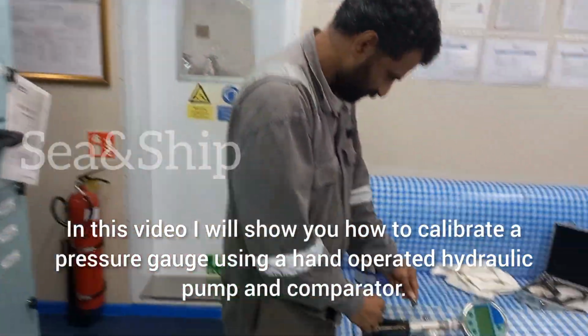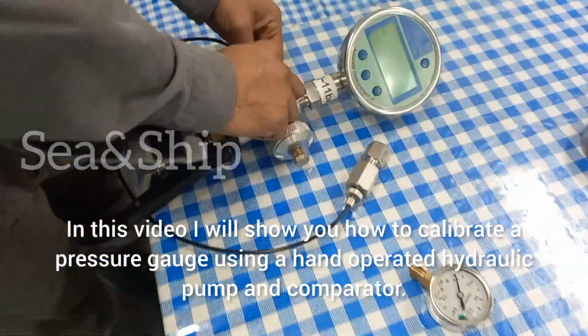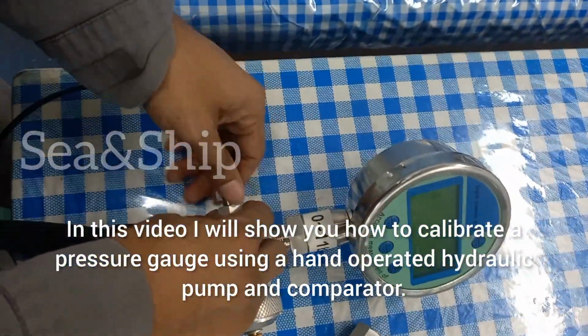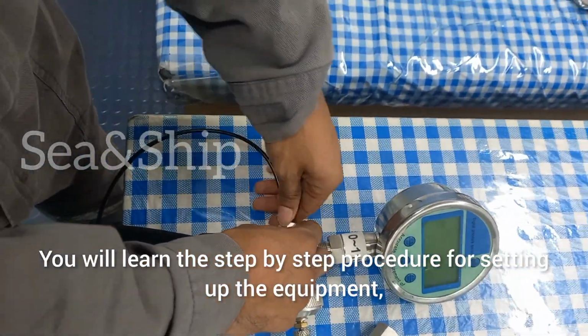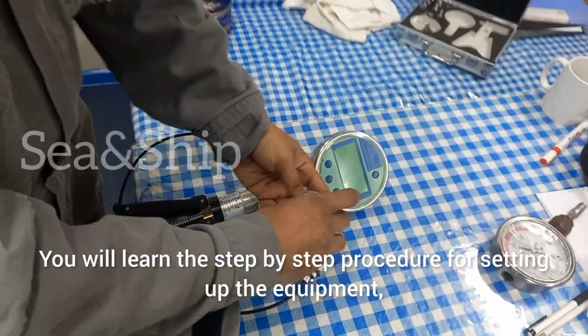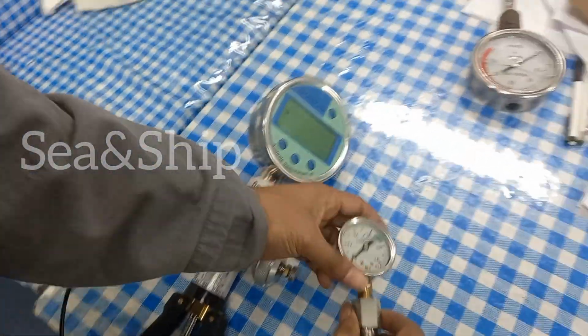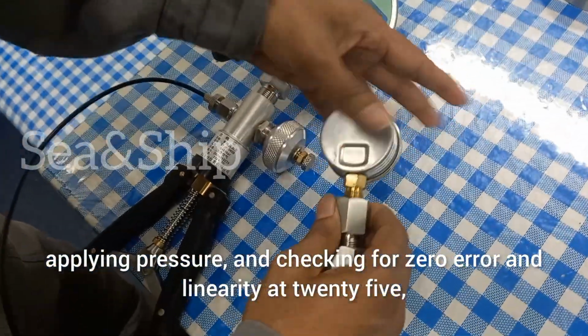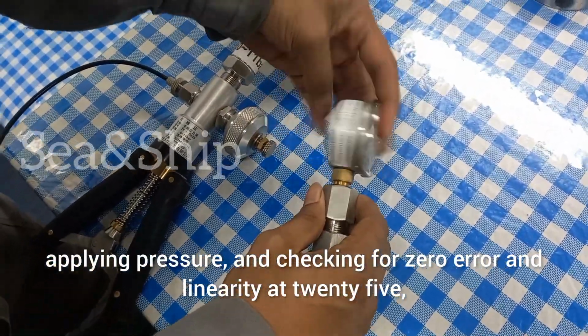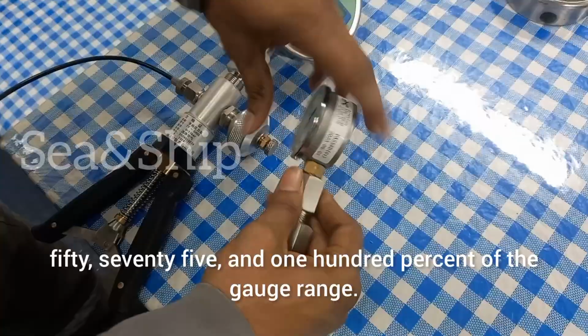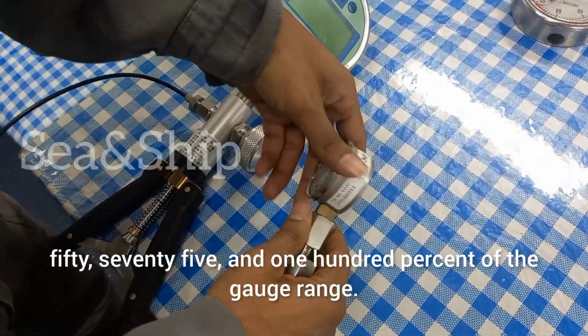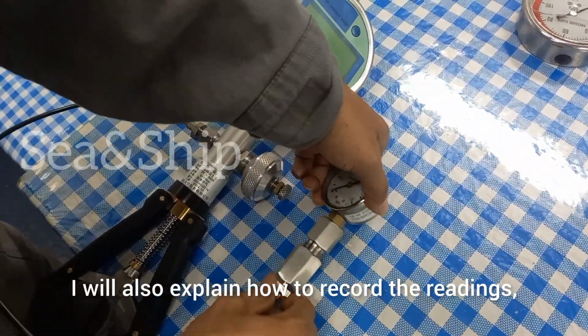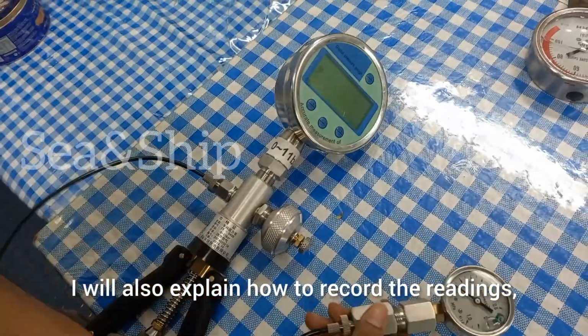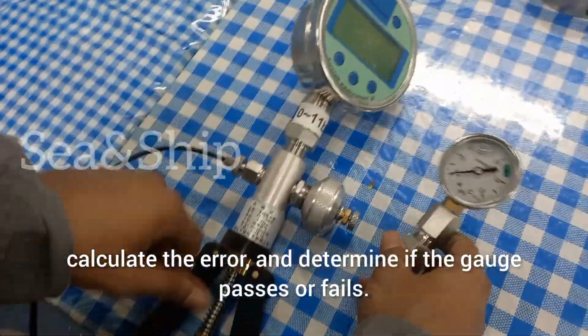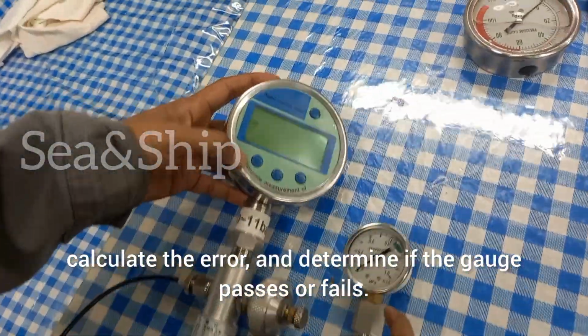In this video, I will show you how to calibrate a pressure gauge using a hand-operated hydraulic pump and comparator. You will learn the step-by-step procedure for setting up the equipment, applying pressure, and checking for zero error and linearity at 25, 50, 75, and 100% of the gauge range. I will also explain how to record the readings, calculate the error, and determine if the gauge passes or fails.